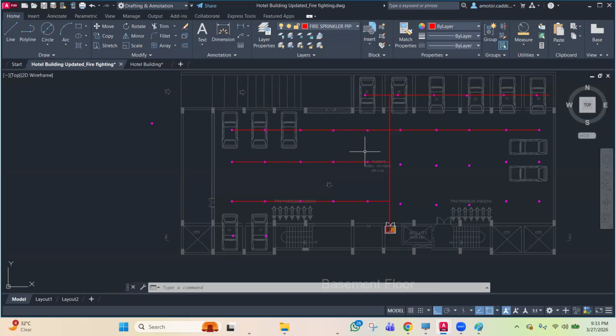Now, regarding the calculation: the sprinkler system calculation is based on density and area of operation of the sprinkler, and we know that flow is density multiplied by area. We use the Hazen-Williams formula for pipe sizing in the sprinkler system, so pressure losses are calculated section-wise. But the curtain system is based on discharge per nozzle, given in liters per minute, and the number of nozzles present.